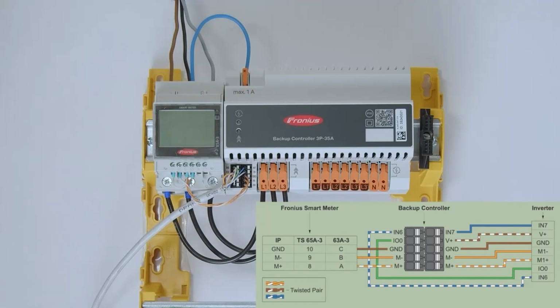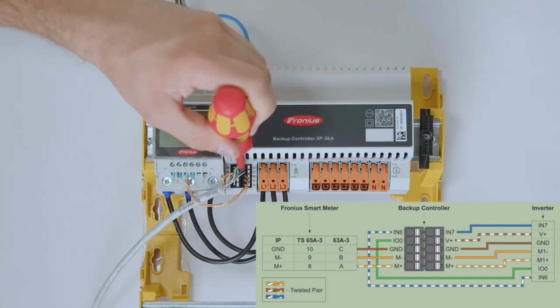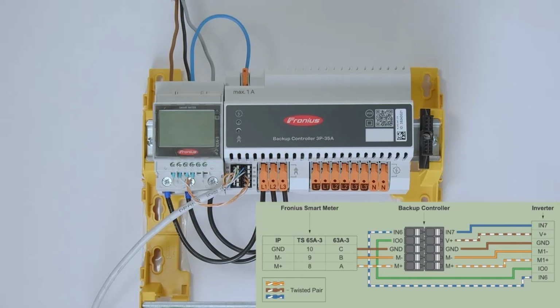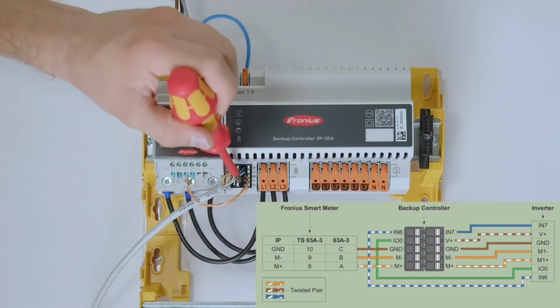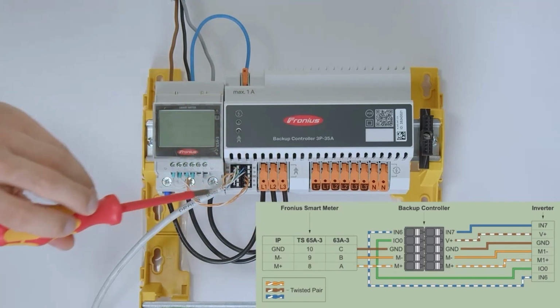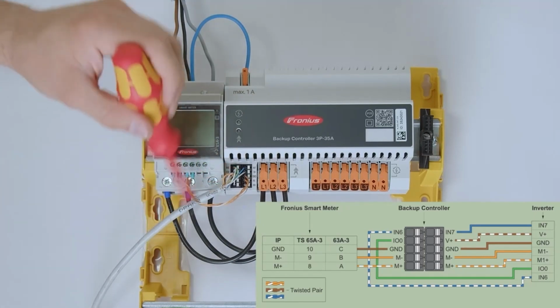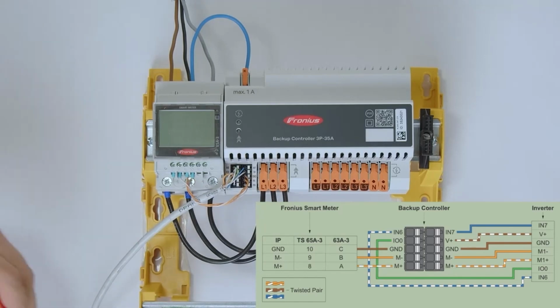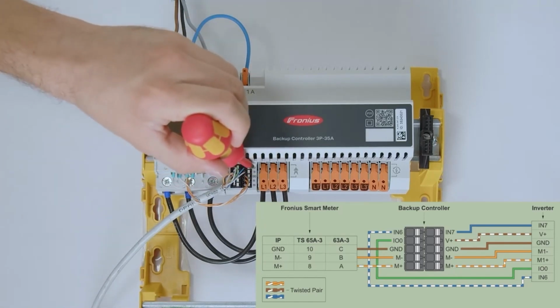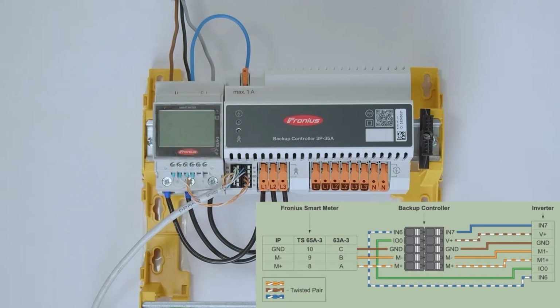Furthermore, we need to have, of course, our data communication to enable the backup mode and to stay in it. So therefore, we have the digital input 6 and input 7, as well as a plus 12 volt signal and our digital IO 0, as well as the ground contact to close the loop. So therefore, you need to cable these contacts to the backup controller so that it can enable the backup mode and stays in it. And therefore you can directly go, for example, like we did it here, with one Cat6 cable, you can directly go to the inverter, to the data communication of the inverter, and on the backup controller you have written down on the data communication interface directly your contacts that you need to install.